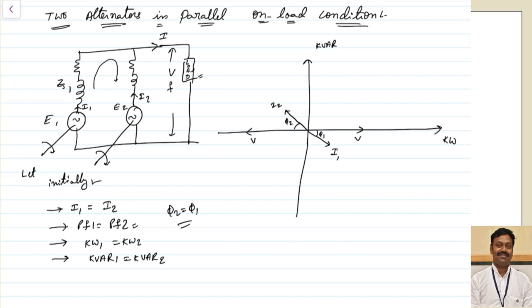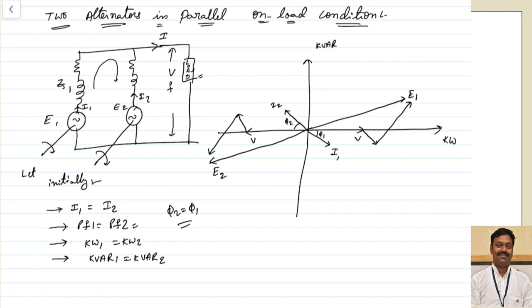To get the value of E, I add I×R and I×X to the voltage. When you add these, you get the value of E1. Similarly for the second generator, adding I×R and I×X, you observe it comes exactly 180 degrees opposite to E1. So E2 is opposite to E1 — within this loop they cancel each other, meaning there is no synchronizing component of current. The I component in phase with the voltage gives I·cos φ, and V×I·cos φ gives active power.